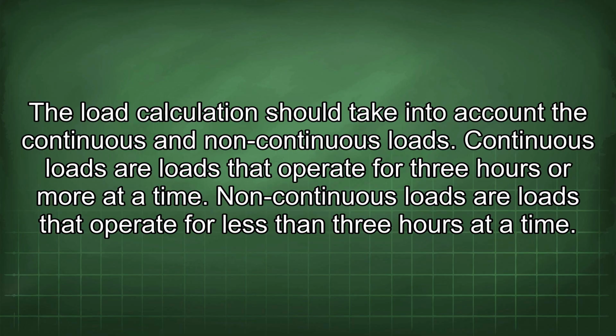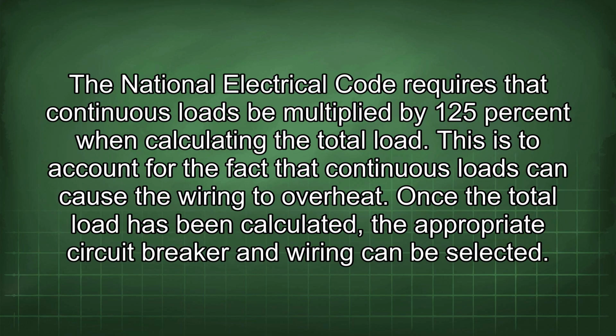Continuous loads are loads that operate for 3 hours or more at a time. Non-continuous loads are loads that operate for less than 3 hours at a time. The National Electrical Code requires that continuous loads be multiplied by 125% when calculating the total load. This is to account for the fact that continuous loads can cause the wiring to overheat. Once the total load has been calculated, the appropriate circuit breaker and wiring can be selected.